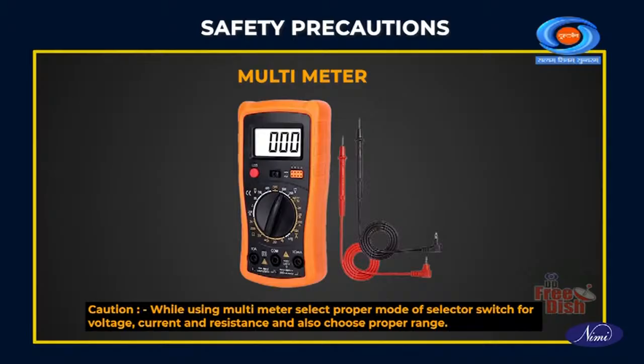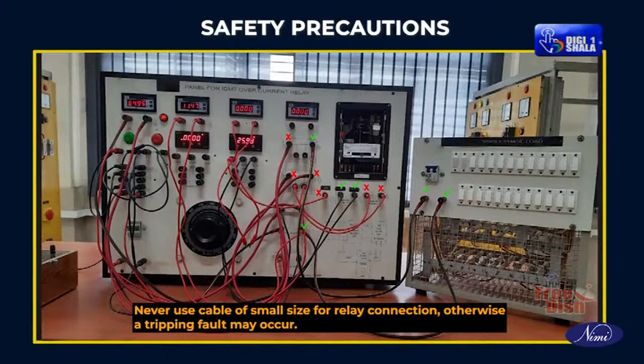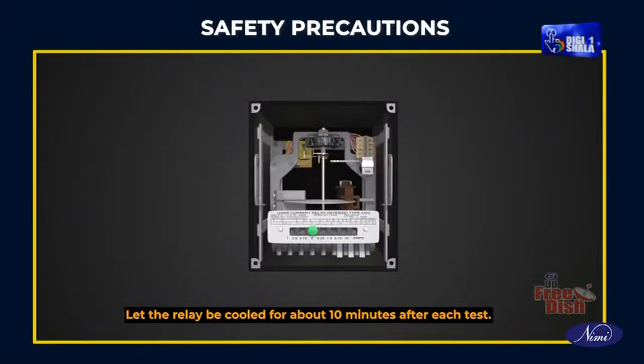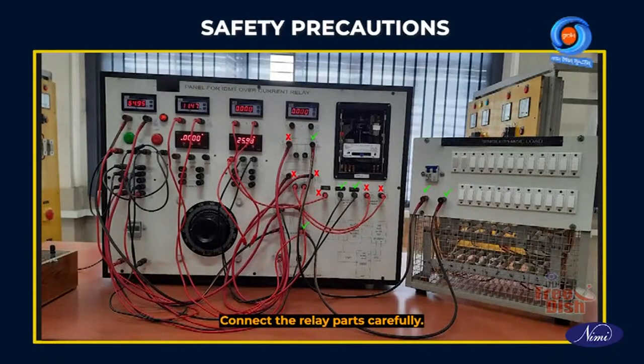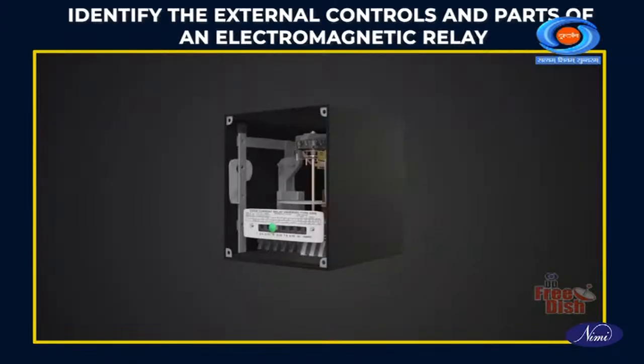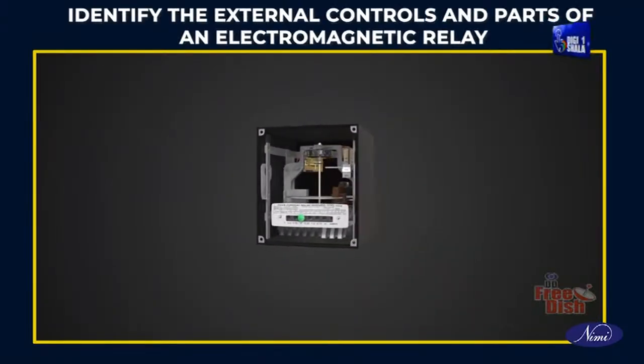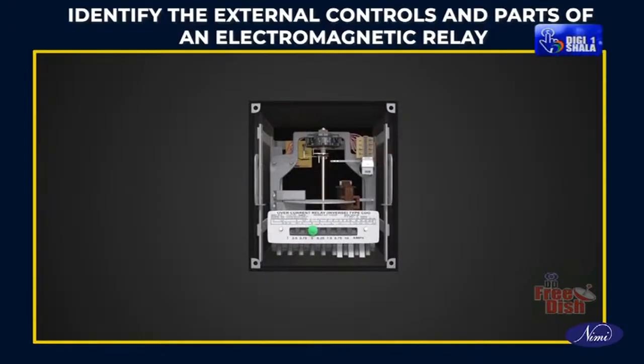Multimeter. Caution: while using the multimeter, select the proper mode of the selector switch for voltage, current and resistance, and also choose the proper range. Never use cable of small size for relay connection, otherwise a tripping fault may occur. Let the relay cool for about 10 minutes after each test. Connect the relay parts carefully. Identify the external controls and parts of an electromagnetic relay.